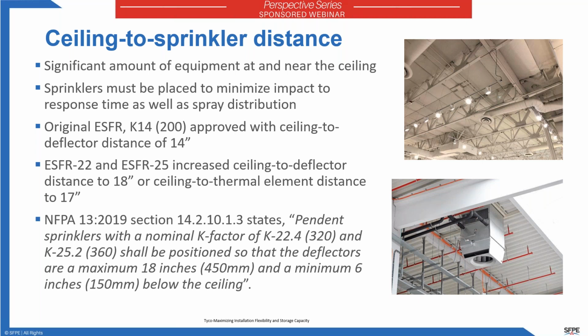So there's ceiling structure up there. There's beams, there's girders, there's purlins, there's vents, there's ductwork, there's heaters, there's air conditioning units, there's lights, there could be fans. So there's a lot of different things up on that ceiling. And unfortunately, you have to make sure that the sprinklers are placed in the proper location to minimize the impact on response time as well as spray distribution.